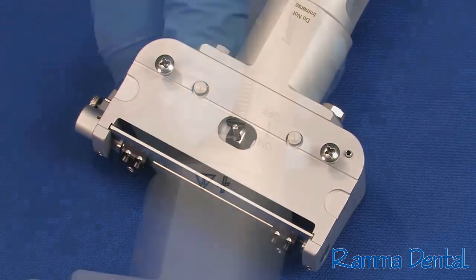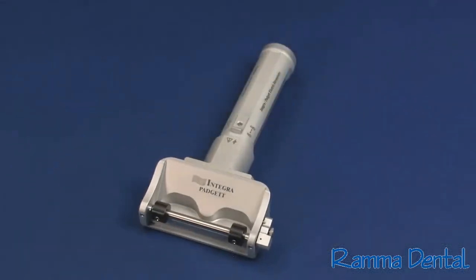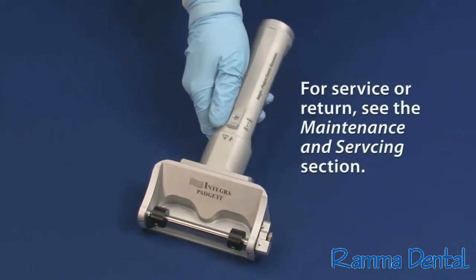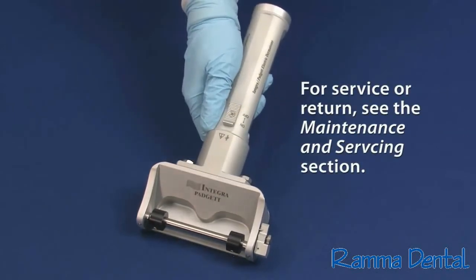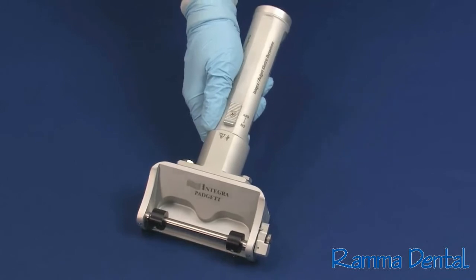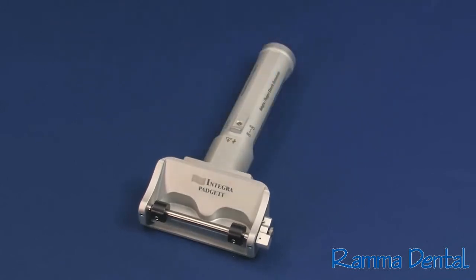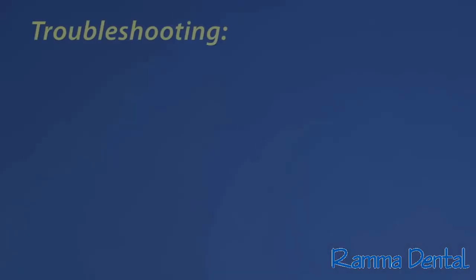If issues are experienced with any of these system checks, do not use the Dermatome and return the unit to the Integra Padgett Dermatome Service Center for service. See the Maintenance and Servicing section. If no issues are observed during this assessment, but performance issues are experienced, refer to the following troubleshooting table. Here are some common problems and possible solutions.